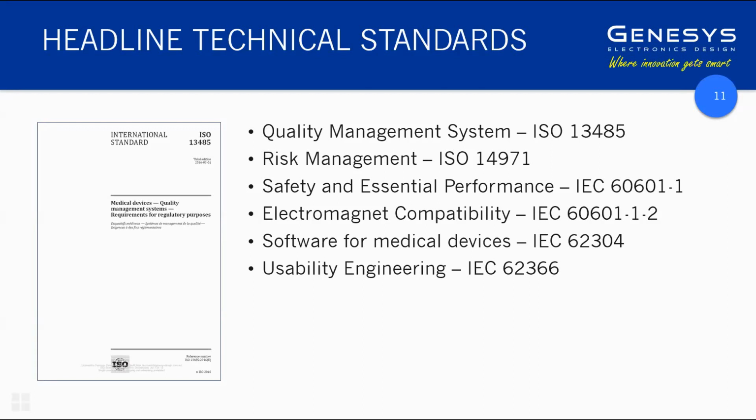Yeah, and I just note the fourth dot point is electromagnetic compatibility, not electromagnet compatibility. My apologies. Getting an ISO 13485 quality system in place is quite burdensome and expensive, and I would suggest, particularly to a startup, don't try and do that at the beginning, because firstly, it's going to distract you from your early stage development work, and secondly, you're not really going to know enough about your product to be able to do it effectively.